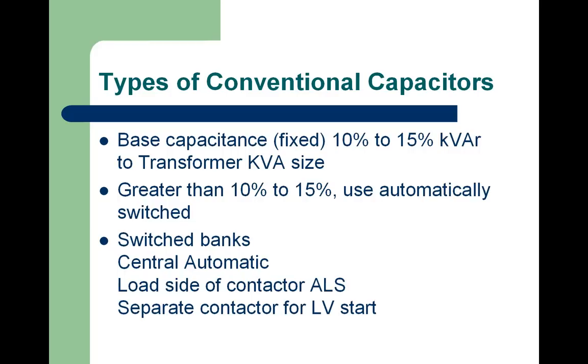150 kVAR on a 1,000 kVA transformer would equate to about a 1%, a little less, 0.85% voltage rise during no load or, let's say, weekend conditions. So on a 600 volt system, if your voltage was 600 volts, you could actually see somewhere around maybe 605, 604 volts with fixed capacitor. The issue sometimes is on the weekends, utility voltages go up, and your 620 volts on the weekend could end up being 625 volts or 624 volts.